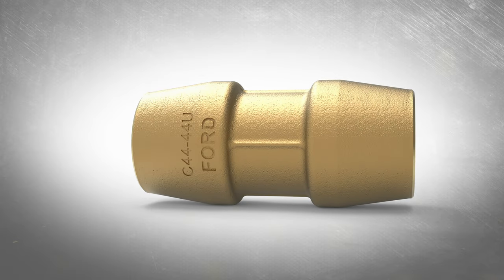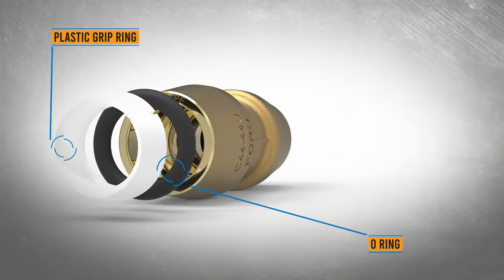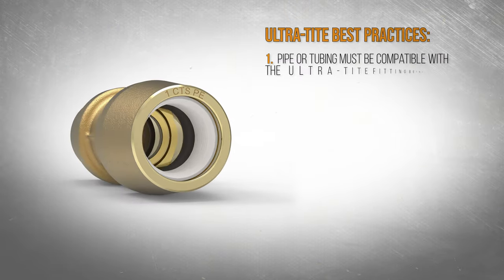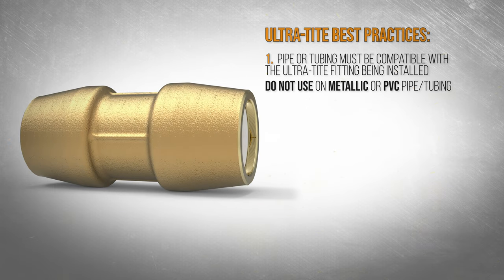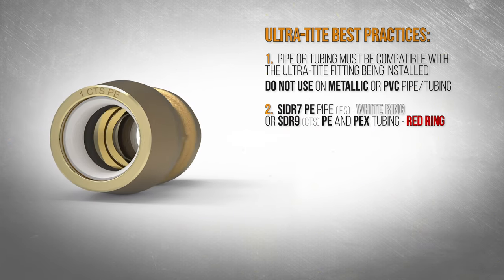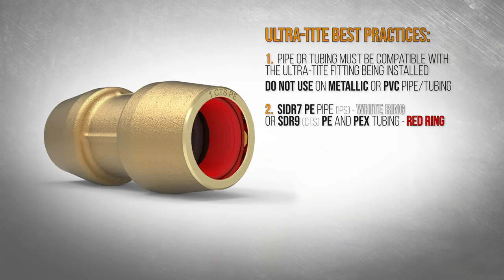The Ford Ultra-Tite is a true stab fit connection for use on plastic pipe or tubing — just insert the line into the fitting to provide an immediate lock. Make sure the pipe or tubing is compatible with the Ultra-Tite fitting being installed. Each fitting is specifically designed to fit either SIDR7 PE pipe or SDR9 PE and PEX tubing.